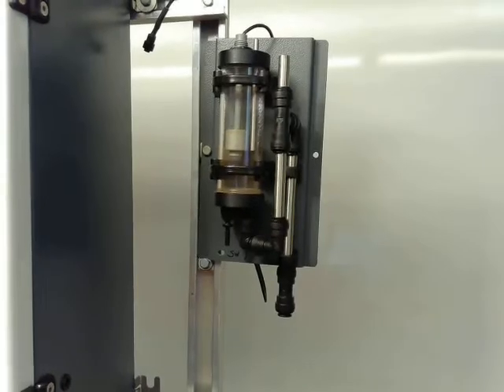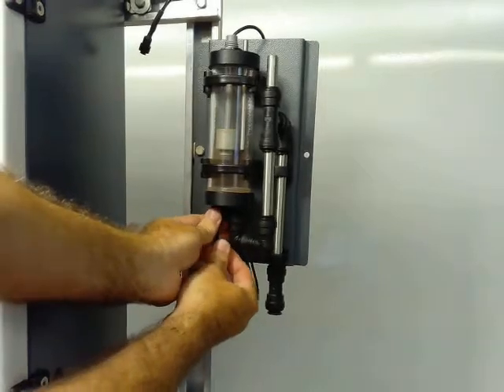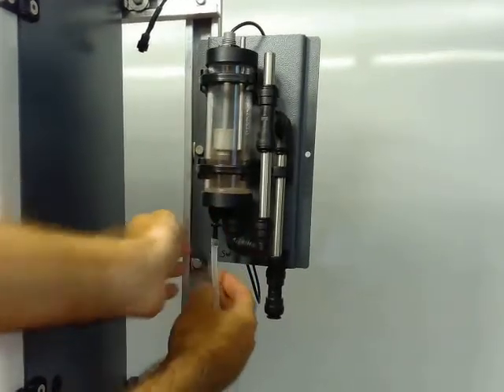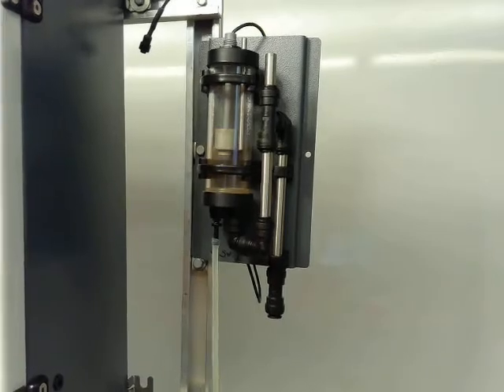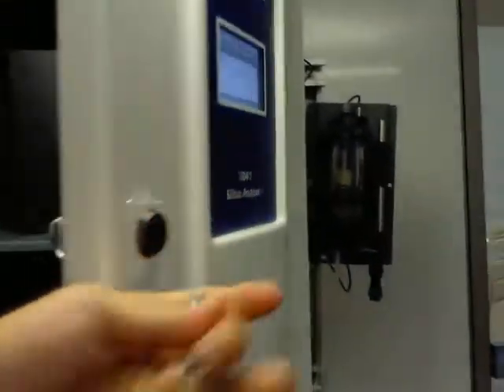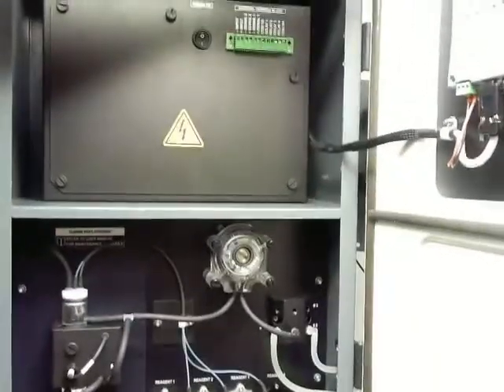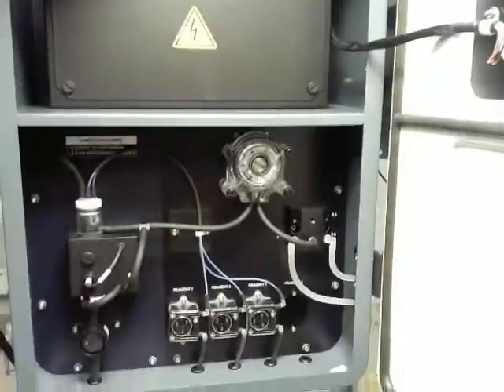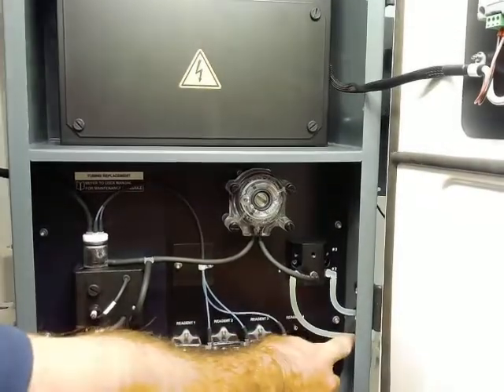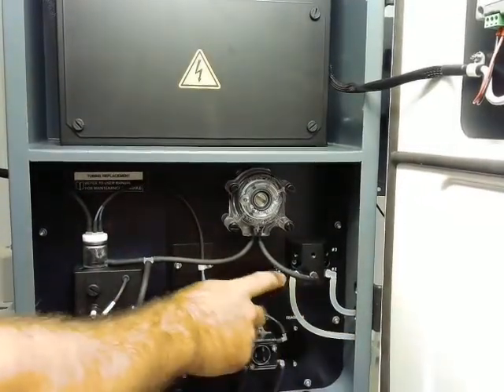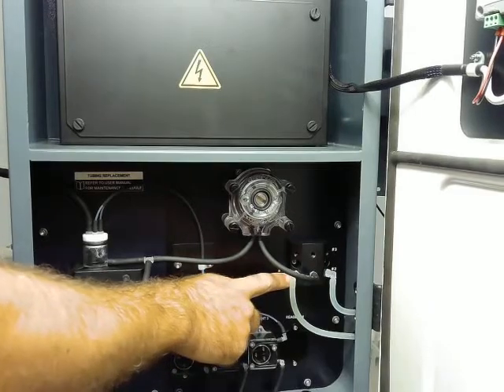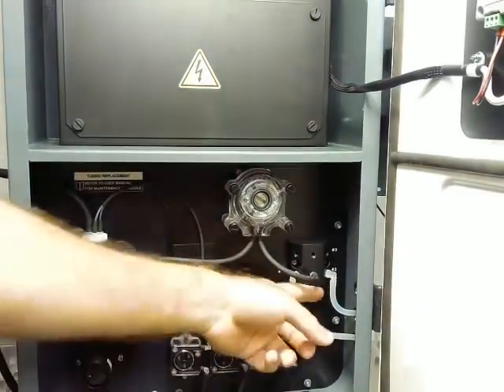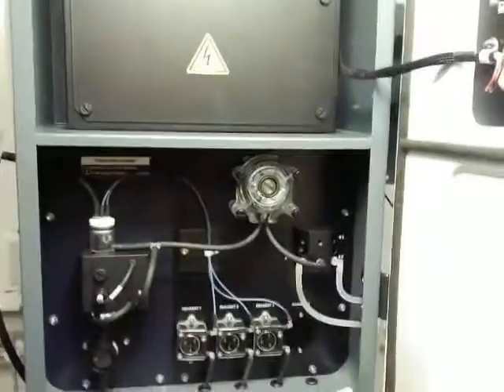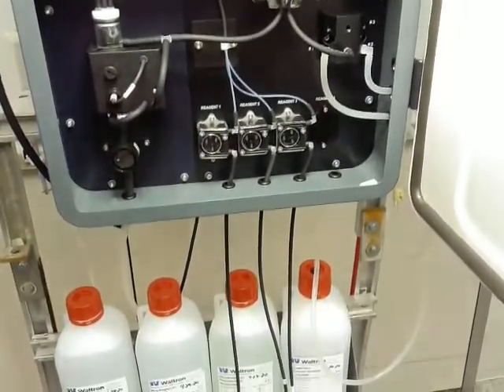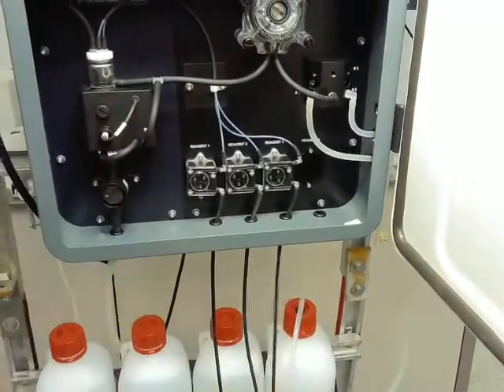Again, in normal operation, you would have your tube to the analyzer connected here. And then this tube is what goes into our analyzer on the inside. Right here. So once that tubing comes in from our sample line, it will go into the number 1 port here on our selection block. And then the number 2 port would be connected to our calibration standard, which in this case goes right down below to our calibration standard here.